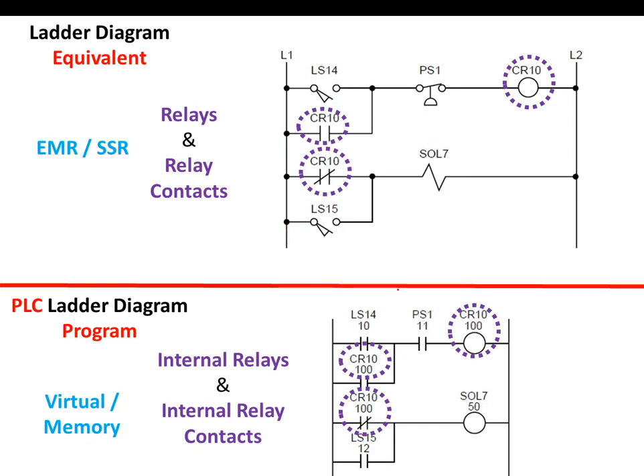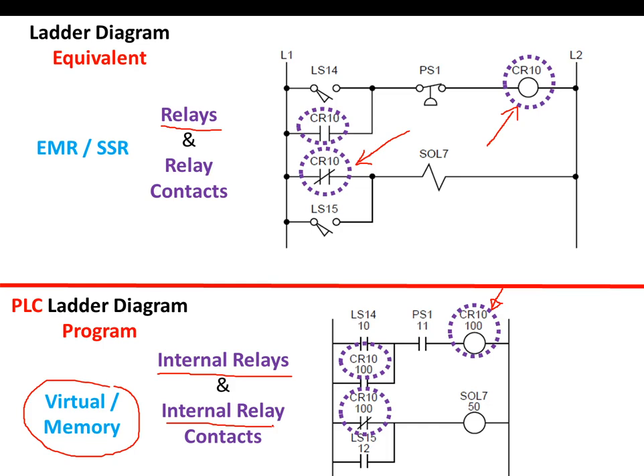There is one more thing left in our discussion: the relays. In every relay logic circuit there are actual relays and actual relay contacts. In the PLC ladder diagram there are no actual relays — these relays are only virtual or memory relays; they are basically software. We term them in the PLC ladder diagram program as internal relays, since they are not physically present — they are internal to the system. That is the reason behind the name.